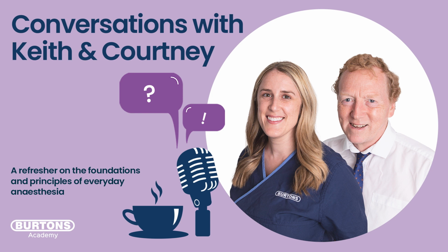Yeah. So if you've got over-damping, that's normally going to be caused by using the wrong tubing. To be fair, there's an incorrect matching between the tubing and the transducer.